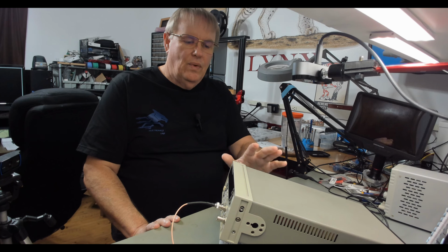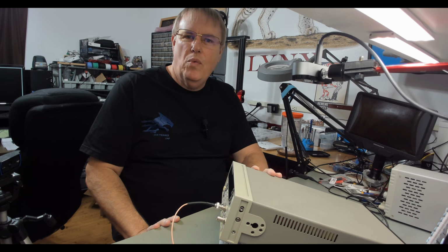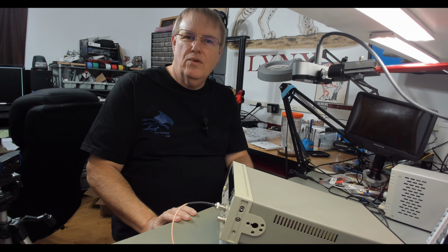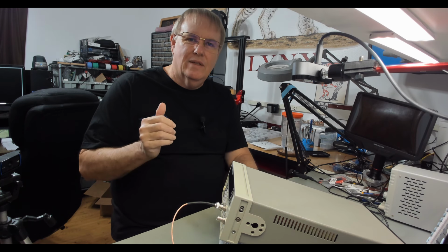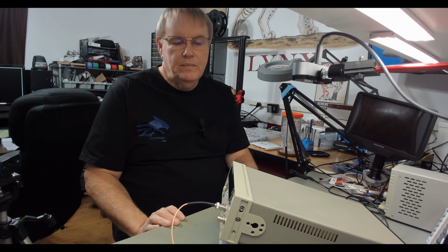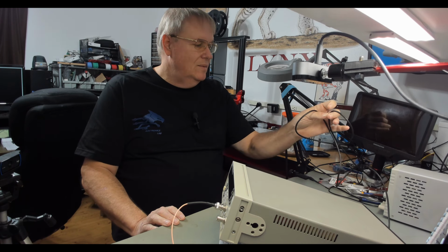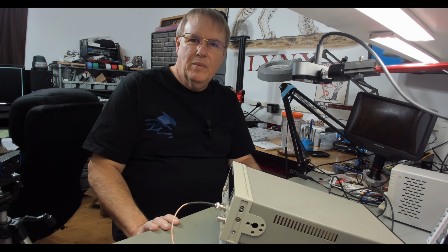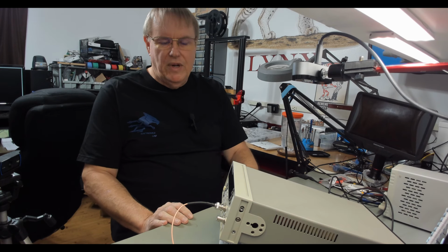And so the way I thought I would do this is it's got a serial port on the back of it, and you can't control it from that serial port, but it will output each reading on that serial port. And that would be good enough for me, at least for the moment. So I've got some serial to USB converters. And so I went online and looked up what I could on using that feature and how to turn it on and such.